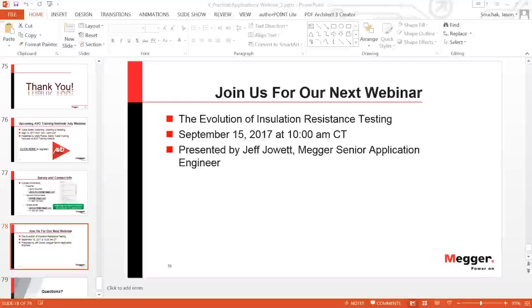All right. Thank you, Jason. Next question is for Henning. If the cable is long, the capacitance increases. Here, according to you, VLF can't be used. Then what should I do? Well, you cannot say VLF cannot be used. The best way to approach this problem is to do a quick calculation of the cable capacitance and then compare that number to the test capability of your test equipment.